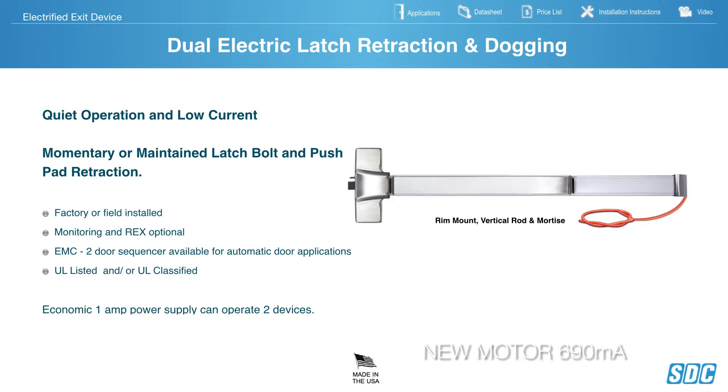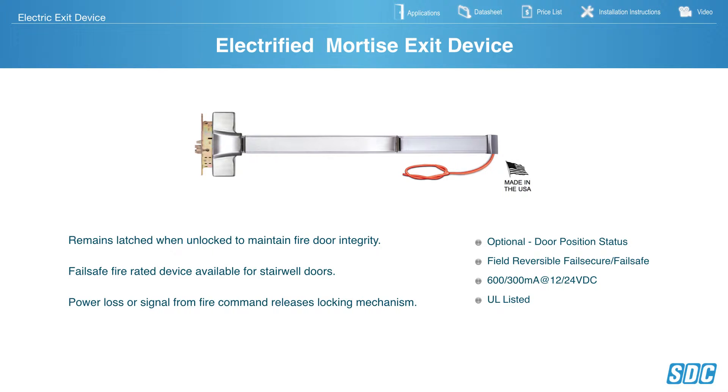SDC Dual Electric Latch Retraction & Dogging, Quiet Operation, and Low Current. These can be factory installed or retrofitted in the field. 690mA latch retraction, 180mA dogging. An EMC Sequencer is also offered — it's a 2-door sequencer available for automatic door applications where it will fire the latch retraction first and then kick on the automatic door operator.